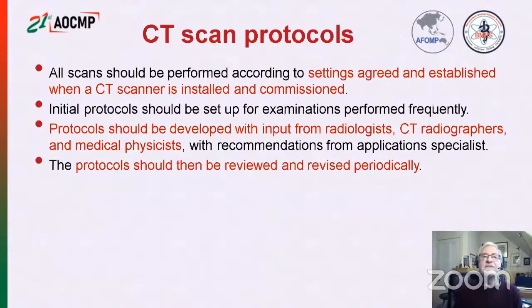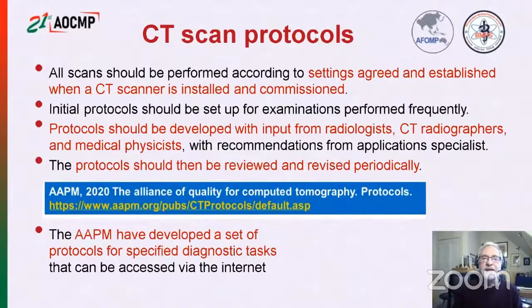So all scans in CT should be performed according to settings agreed and established when a CT scanner is installed and commissioned. The initial protocols should be set up for examinations performed frequently, and protocols should be developed with the input from radiologists, CT radiographers and medical physicists. And the protocols should then be reviewed and revised periodically. And as a guide, initially when setting up protocols, the AAPM have developed a set of protocols for specified diagnostic tasks that can be accessed via the internet.